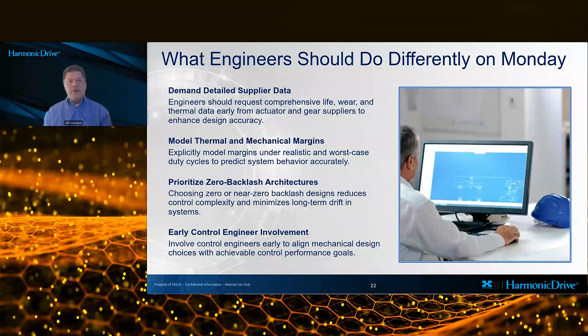And what should engineers do differently on Monday? From a practical standpoint, engineers working on medical systems can take several immediate actions to improve reliability outcomes. First, demand detailed life, wear, and thermal data from actuator and gear suppliers early in the design process, rather than relying solely on nominal ratings. Second, explicitly model thermal and mechanical margins under realistic duty cycles, including worst-case scenarios.